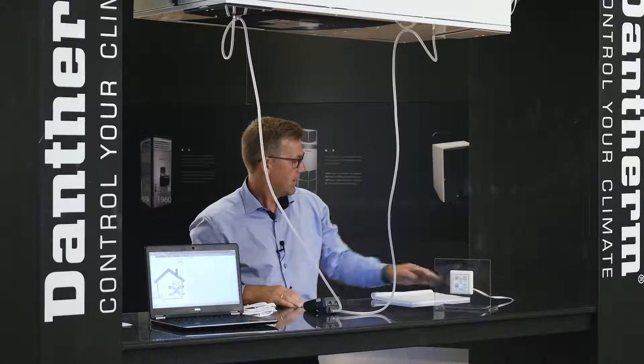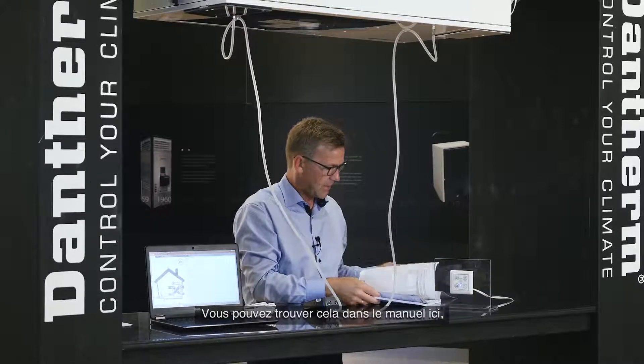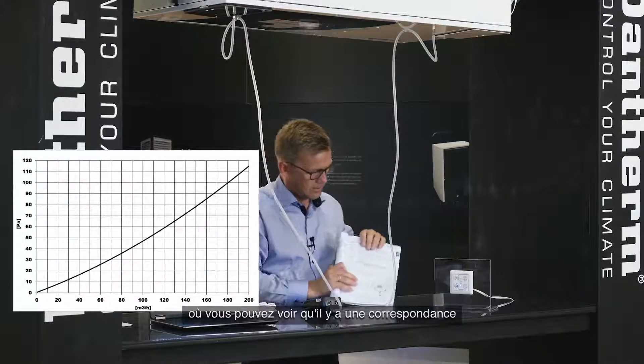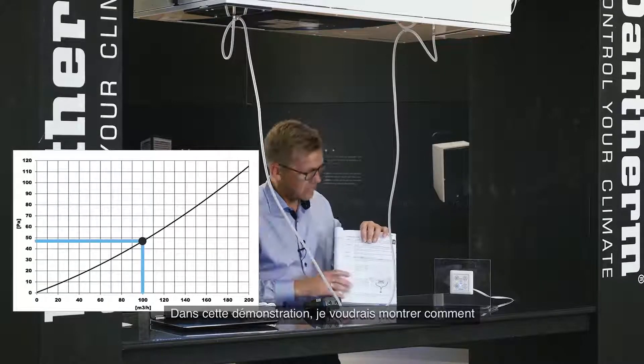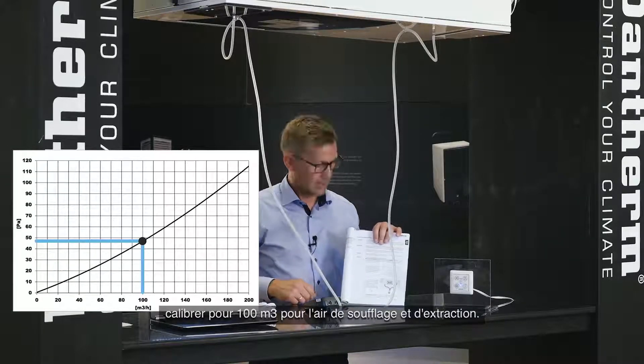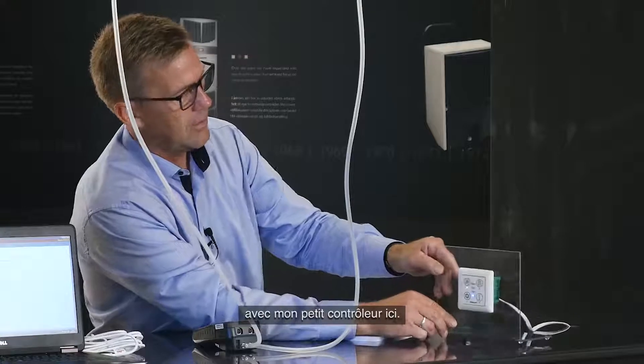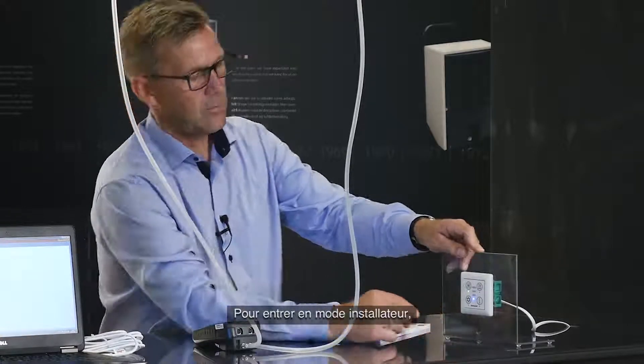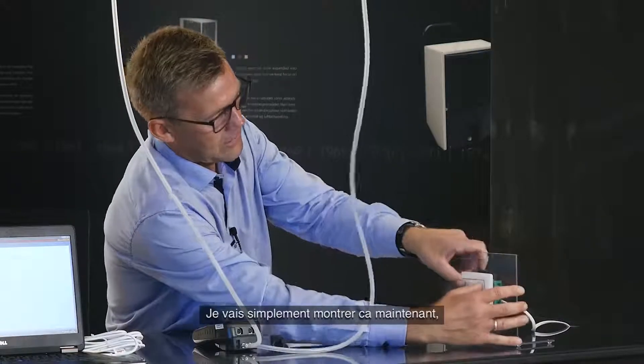I'll demonstrate how to calibrate it using the wired controller. First, look up in the manual to find the airflow you need — there is a correspondence between the delta P over the heat exchanger and the airflow. In this demonstration, I'll calibrate for 100 cubic meters per hour for supply air and extract air. To enter installation mode, press both the manual speed and the week program speed buttons at the same time for five seconds.